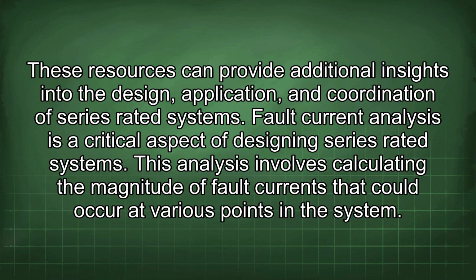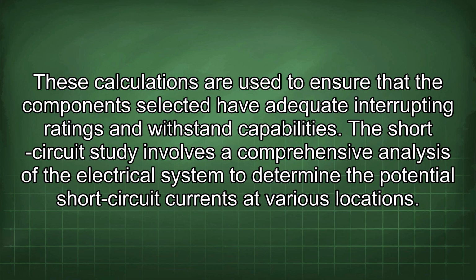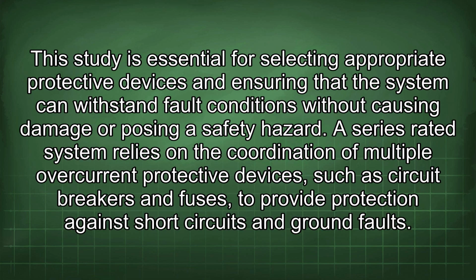Fault current analysis is a critical aspect of designing series-rated systems. This analysis involves calculating the magnitude of fault currents that could occur at various points in the system. These calculations are used to ensure that the components selected have adequate interrupting ratings and withstand capabilities. The short circuit study involves a comprehensive analysis of the electrical system to determine the potential short circuit currents at various locations. This study is essential for selecting appropriate protective devices and ensuring that the system can withstand fault conditions without causing damage or posing a safety hazard.